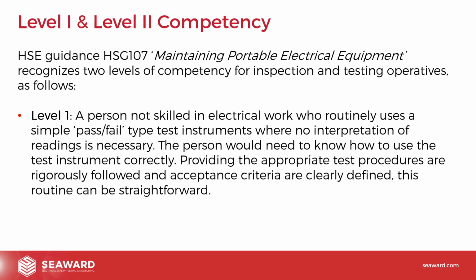So they define a level 1 person as a person not skilled in electrical work who routinely uses a simple pass-fail type test instrument where no interpretation of the readings is necessary. The person would need to know how to use the instrument correctly, providing the appropriate test procedures are rigorously followed and acceptance criteria clearly defined. This routine can be straightforward. So what they're including in here is provision for a person who is still competent, but is not electrically trained, a person with a lesser degree of training. But because they're using a very simple go, no-go type test, or something like a Seaward Prime Test 50, and presumably they're testing within quite tight boundaries, so they're testing a limited range of equipment that they're very familiar with and have been trained on.